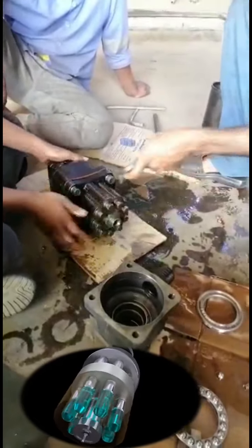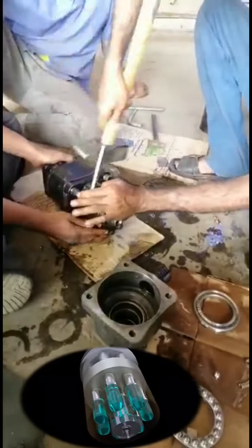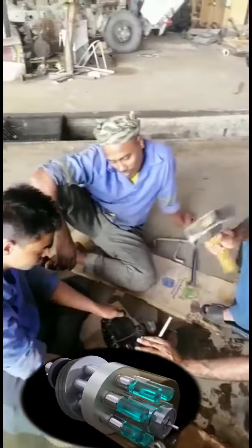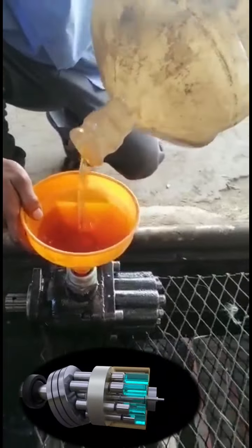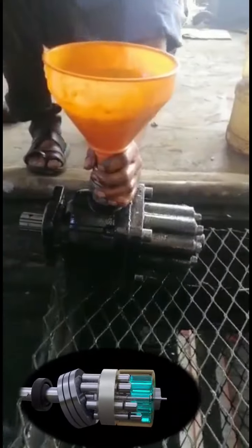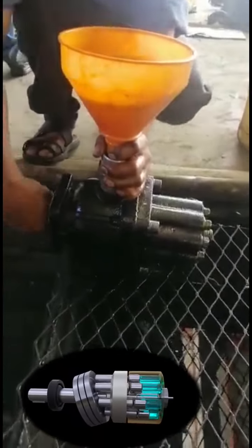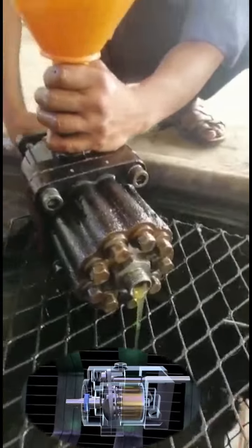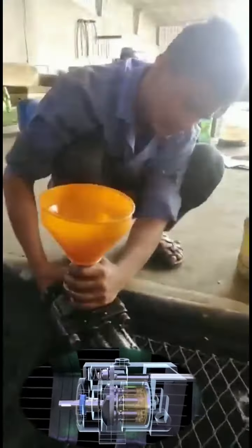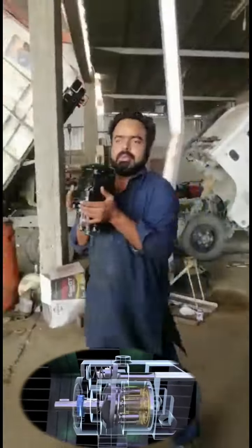to the discharge channel. The pumping capacity of an axial piston pump is determined by the number and diameter of its pistons, the space between them in the block, as well as their stroke. The stroke of the pistons is determined by the angle of inclination of the bent axis, or the swash plate. The longer the stroke, the greater the pumping capacity. By changing the angle of inclination of the swash plate, you can influence the stroke, thus regulating the pumping capacity. We will try to explain pump regulation in one of our videos.